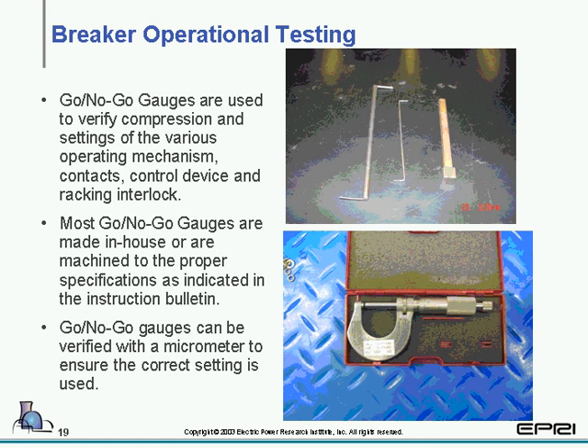Go, no-go gauge testing. Most manufacturers have them in their instruction manual, and we've shown you in the upper picture how they were made: they're actually using a drill bit, ground, and then soldered or welded onto an end of a rod. And when you make a piece of equipment like this, you need to check it. Obviously we show you below that you want to use a micrometer to verify that it's within the tolerances or spec of the manufacturer, because after multiple uses, you can actually reduce the size.